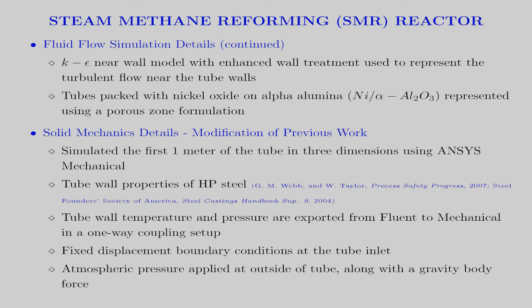The temperature results are shown here for the case of a cyber attack. The figure on the left shows the temperature profile near the inlet end of the tube at the start of the simulation, where the process is operating at steady state. At 0.1 seconds, a cyber attack that targets the sensor is activated. The sensor reading is detected to be a low value, which causes the controller to increase the temperature to the maximum bound in response. The consequences of this attack can be seen in the figure on the right.